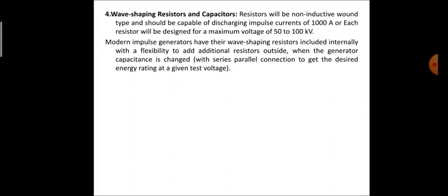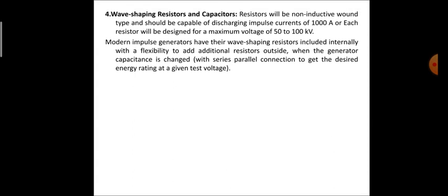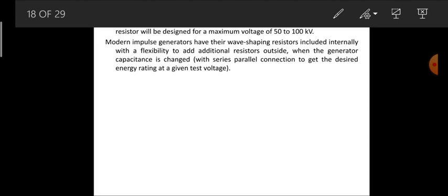Okay, so the resistors, as I said, will be non-inductive type, and they should be capable of discharging impulse currents of 1000 amperes each, or more. Here each resistor will be designed for a maximum voltage of 50 to 100 kilovolt. As I said, the resistances would be non-inductive.